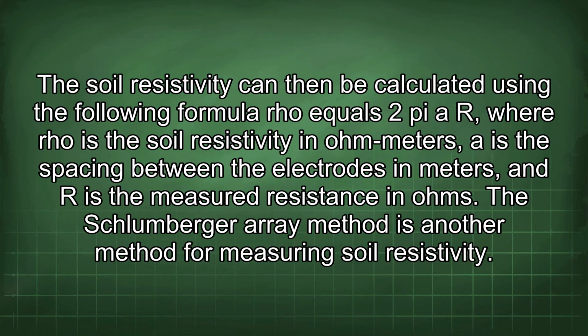The soil resistivity can then be calculated using the following formula: ρ equals 2 pi a r, where ρ is the soil resistivity in ohm meters, a is the spacing between the electrodes in meters, and r is the measured resistance in ohms.